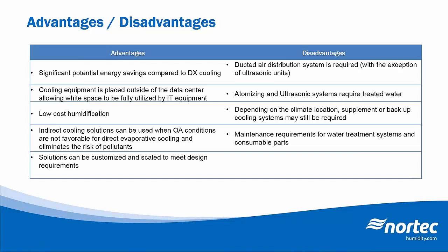So now that we've looked at the different technologies, let's take a look at some of the advantages and disadvantages of using an adiabatic system for cooling and potentially humidification. So let's start with the advantages. The clear advantage here is potential energy savings compared to traditional DX cooling. So depending on your climate location, you may be able to completely eliminate the need for mechanical cooling itself. And even if you can't operate the system on economizer with evaporative assist year round, there still may be considerable savings by reducing the operational hours of the DX cooling system.